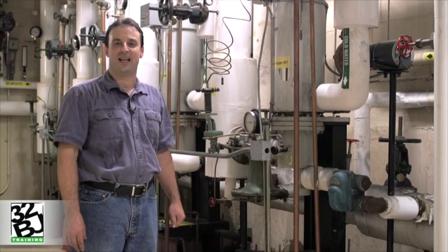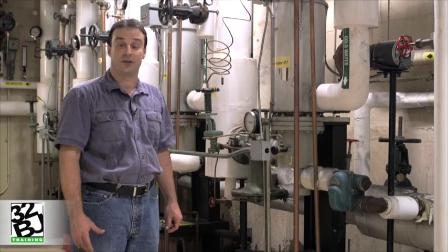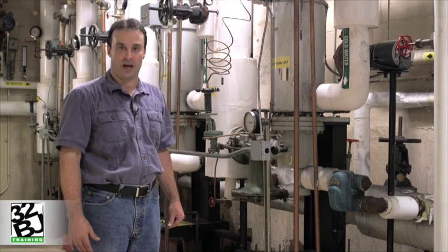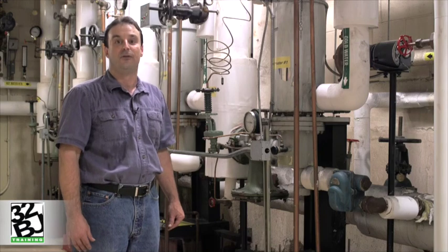Some of the qualities of the semi-instantaneous hot water heater that make it so advantageous is its relatively small footprint, but its ability to have a rapid recovery rate and keep up with very high demand for domestic hot water loads inside the building. In summary, the efficiencies of the semi-instantaneous hot water heater vary greatly based on the steam production and how efficiently it is being produced. Other efficiencies, like motor efficiencies surrounding the pumps, piping insulation, and also steam trap maintenance, are important components that will vary the efficiency of the semi-instantaneous hot water heater.